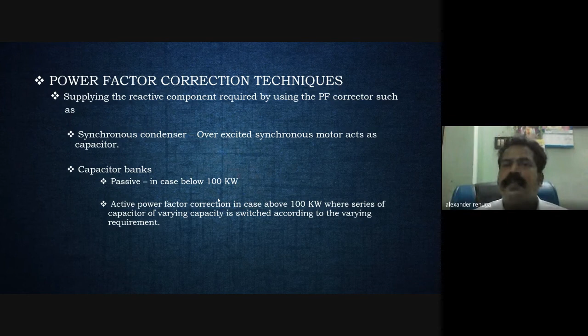For a connected load of less than 100 kilowatt, we can use capacitor banks, that is, passive correction only. Beyond 100 kilowatt, we can use active power factor correction techniques. In that, we need the same capacitor bank, but with switching techniques, which can automatically change the number of capacitors, that is, the capacitance value. The other one is the synchronous condenser. In many industries where a large number of motors are used, they use a synchronous motor as a capacitor to compensate for the power factor deviation.